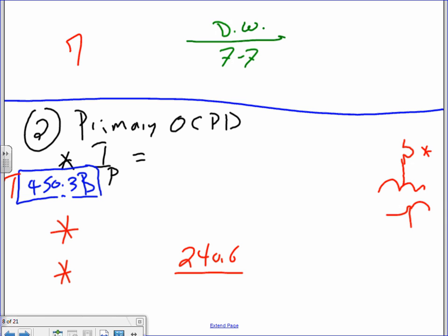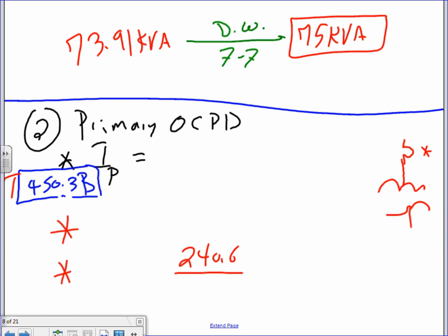I have my 73.91 kVA. Derek, get me the size of that baby. What's your next standard? From page 7-7? Thank you, 75. So the next standard is 75 kVA transformer. So gentlemen, you grab a 75 kVA transformer, drop it for this project. I can't remember what we did in Revit. If we did, we still have to revisit the calculation, remember. So I'm not worried tomorrow because you need to plug in your actual receptacles after you design it. Okay, that's 75 kVA, guys, done.